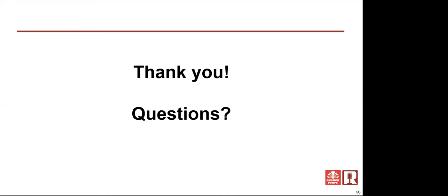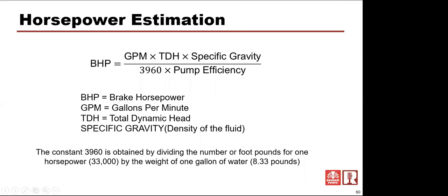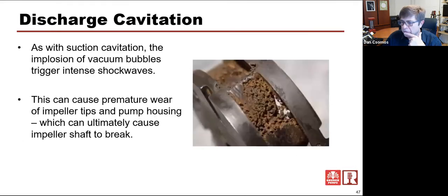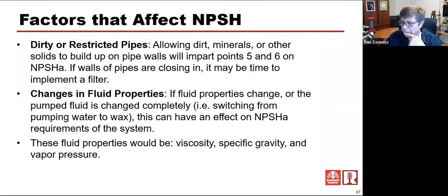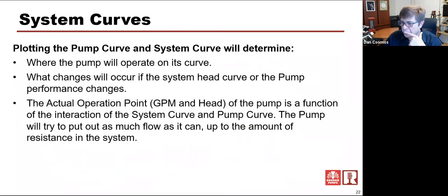Hey, Dan, can you explain, you had a slide that was talking about diagnosing issues within the pump, and it said something about the uses of amps. Sure. All right. So basically, when we take an amperage reading, we can then convert that amperage reading to brake horsepower. And if we go back to the performance curve itself, let me try to get back there. It was a long way back in this presentation.